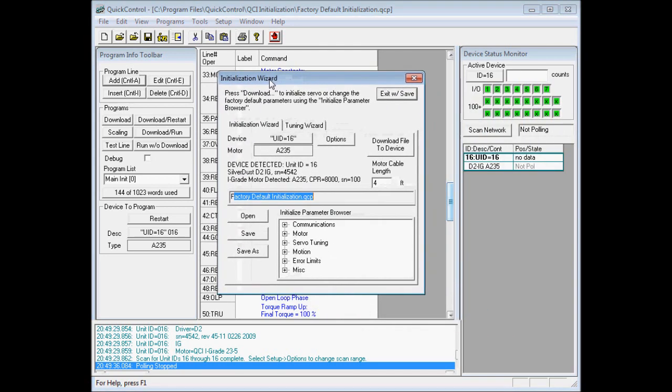In the initialization wizard, we then enter the motor cable length. Knowing the length of the motor cable, the controller can then compensate for the voltage drop across the motor cable. I have a 10-foot motor cable, so I'll enter 10 feet.